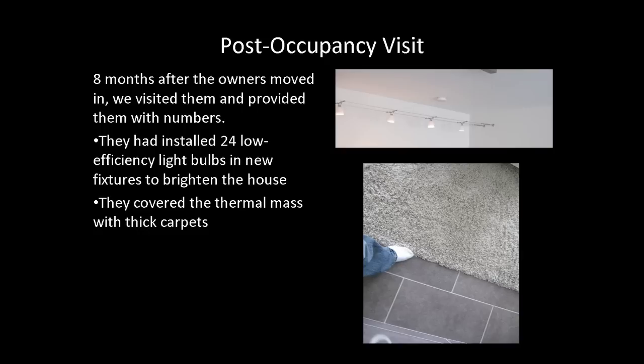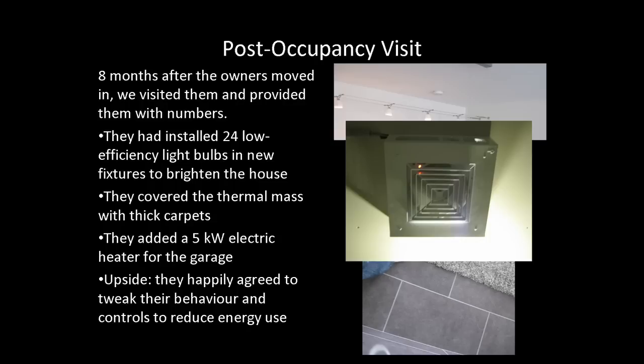Now, I can understand why they would do this. They probably felt that the floor is a little cold on their feet, and so they wanted to make things more comfortable. Finally, they converted the garage, which was originally intended just to store a single car, into a workshop. Well, to keep things warm, they installed a 5-kilowatt electric heater. The problem is this electric heater is only about a quarter as efficient as the heating system for the house.